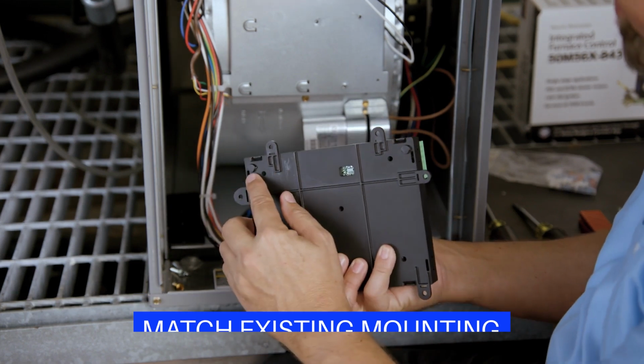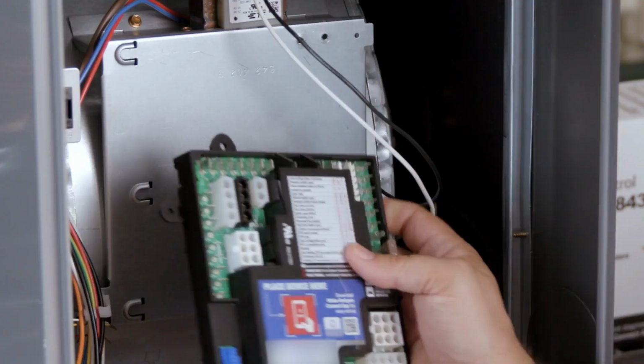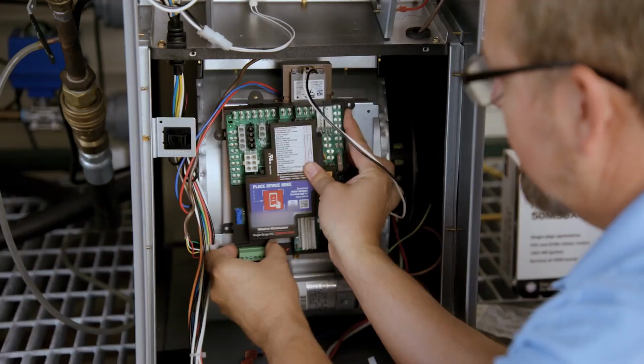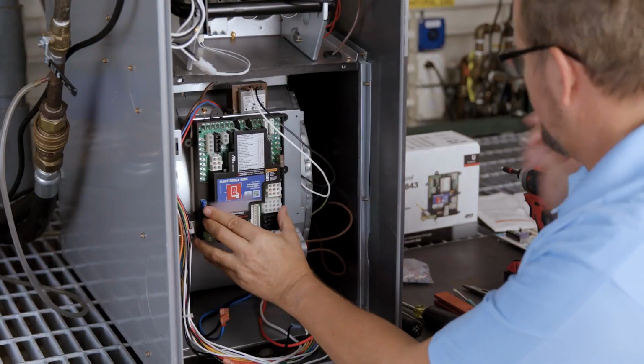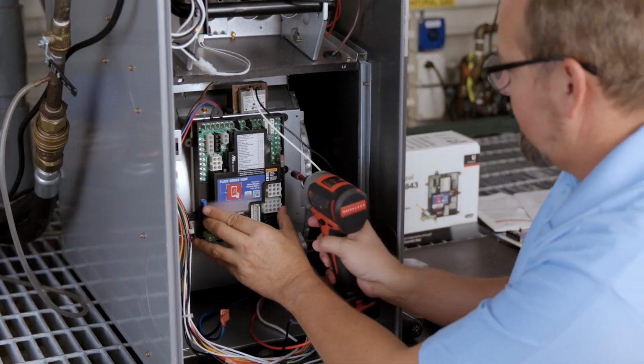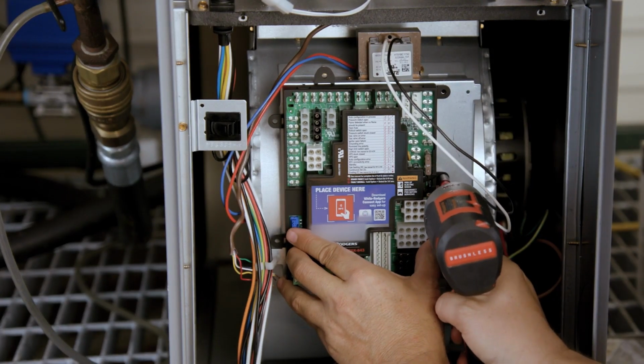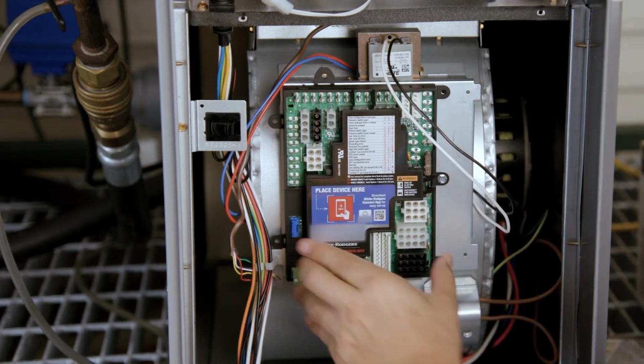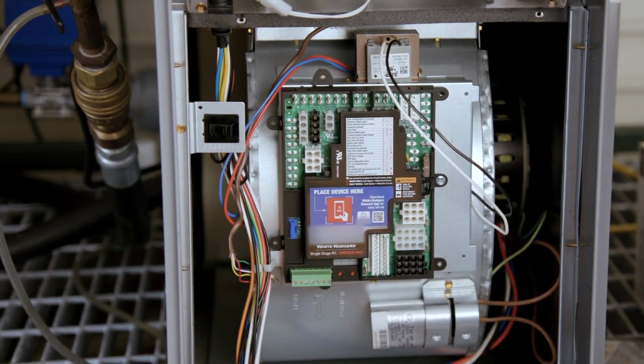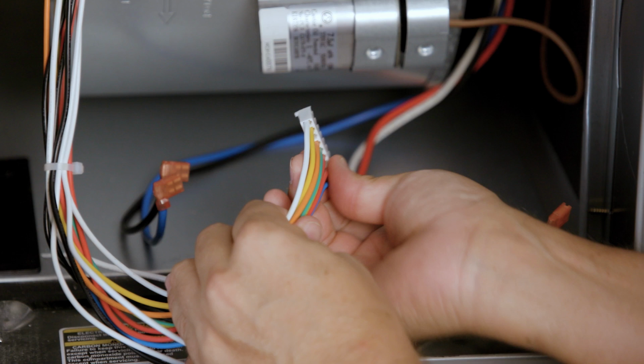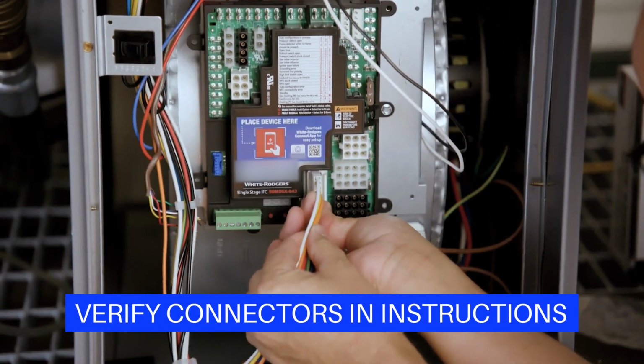Mount the 50M56X-843 in the unit. For this application, the slide-in tabs are used with one of the mounting tabs, utilizing the same mounting configuration of the previous control. Make sure you don't damage any components such as wire harnesses or blower wheels when drilling or installing screws. Identify the main connector on the OEM wiring harness and attach it to the matching connector on the new control. Use the wiring diagrams in the installation instructions for proper OEM connector and wire identification.